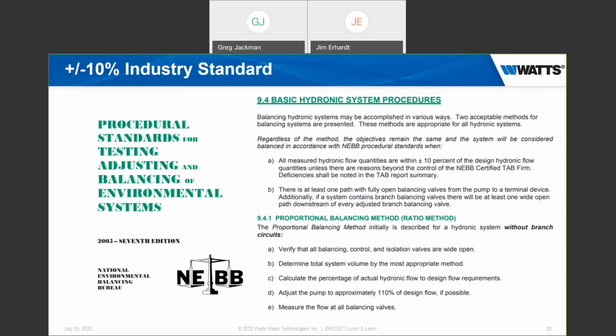In regards to the wet side, the hydronic side, section 9.4, second paragraph down, you'll see there's a couple of different methods that are appropriate for all hydronic systems, but you'll see in italics, regardless of the method, the objectives remain the same and the system will be considered balanced in accordance to NEBB procedural standards when, bullet point A, take a look at that, all measured hydronic flow quantities are plus or minus 10% of the design. So there it is. That's where it comes from. It's the standard that is used for balancing systems.